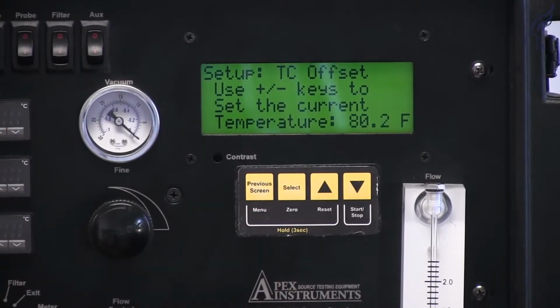For this calibration, we'll need a calibrated reference TC simulator. We'll plug this simulator into one of our channels. In this case, the stack channel. I've set my reference TC simulator to 1000 degrees, but it's recommended to set your reference TC simulator to the upper range that you're likely to experience out in the field.